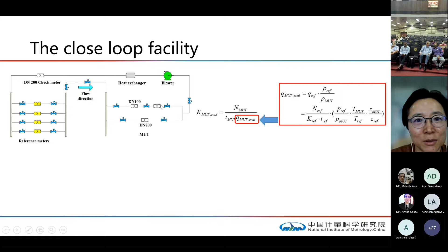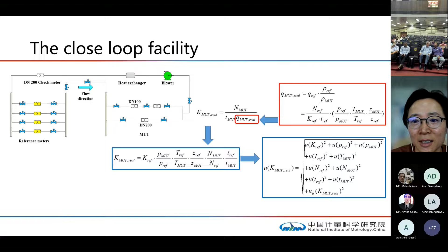When the closed loop is used, you can see the gas will flow in these directions. The meter under test is mounted downstream of the master meter. The principle of the closed loop facilities is similar to the sonic nozzle facilities. So finally, the total uncertainty is like this.